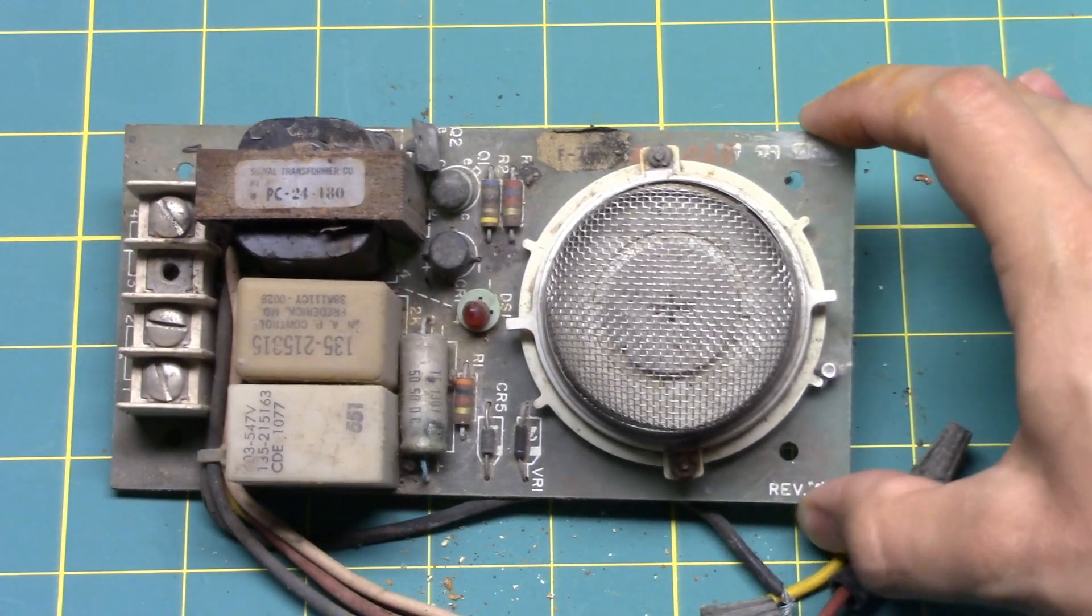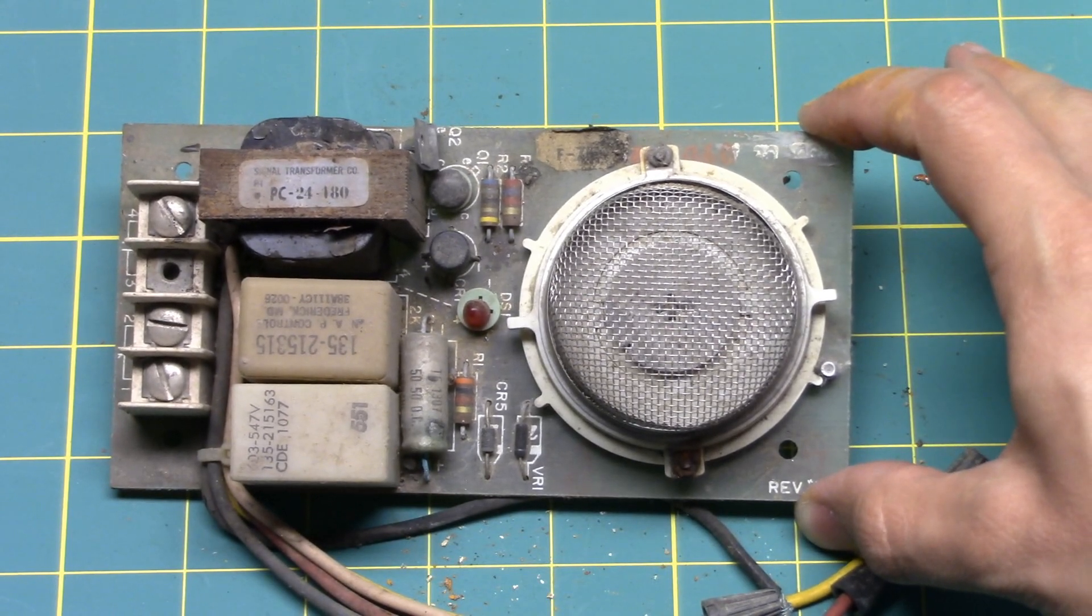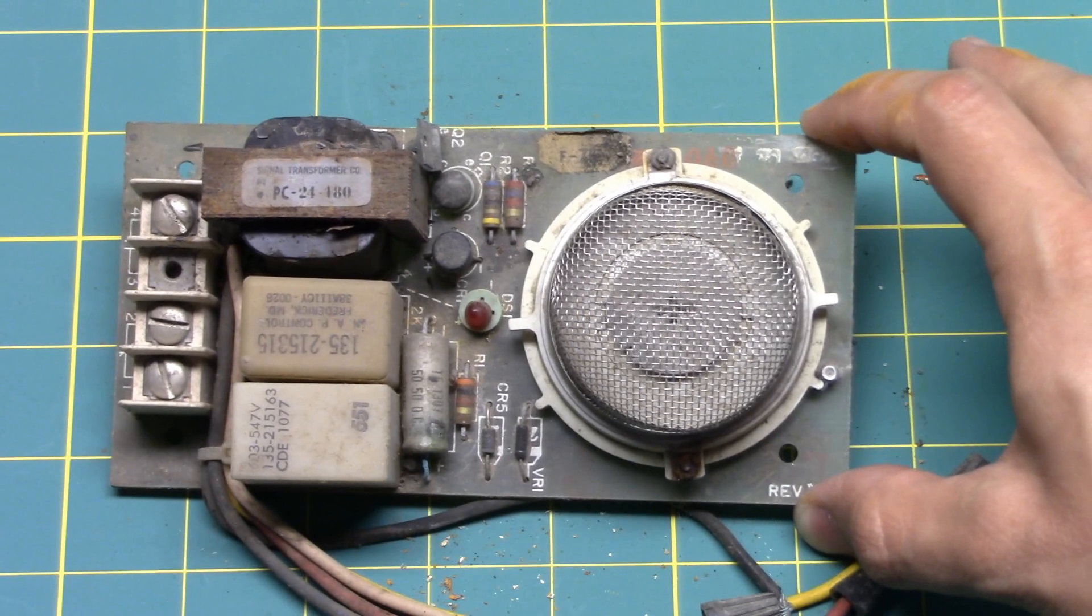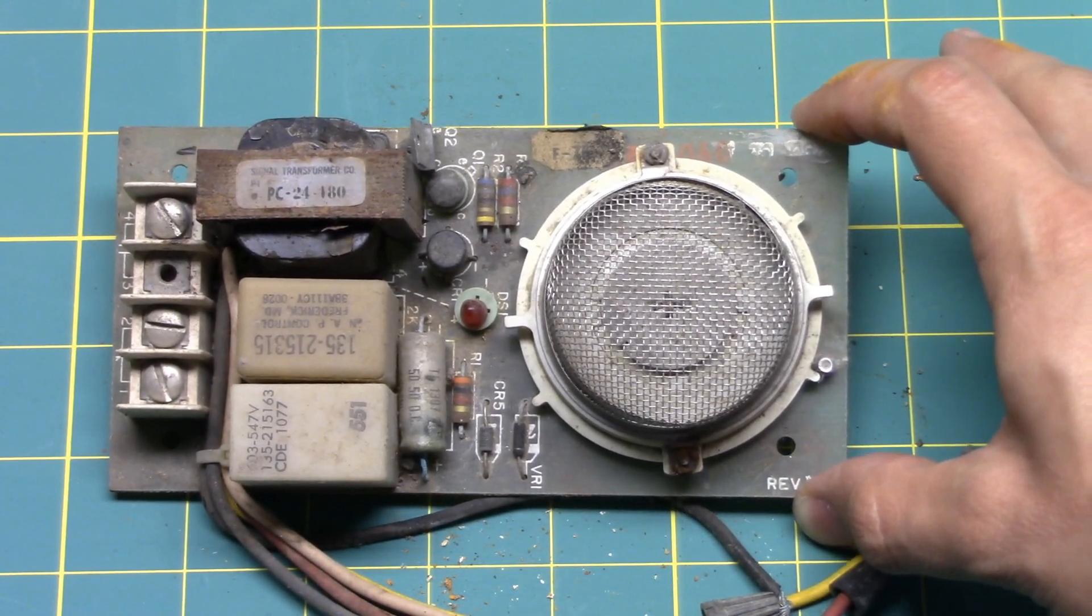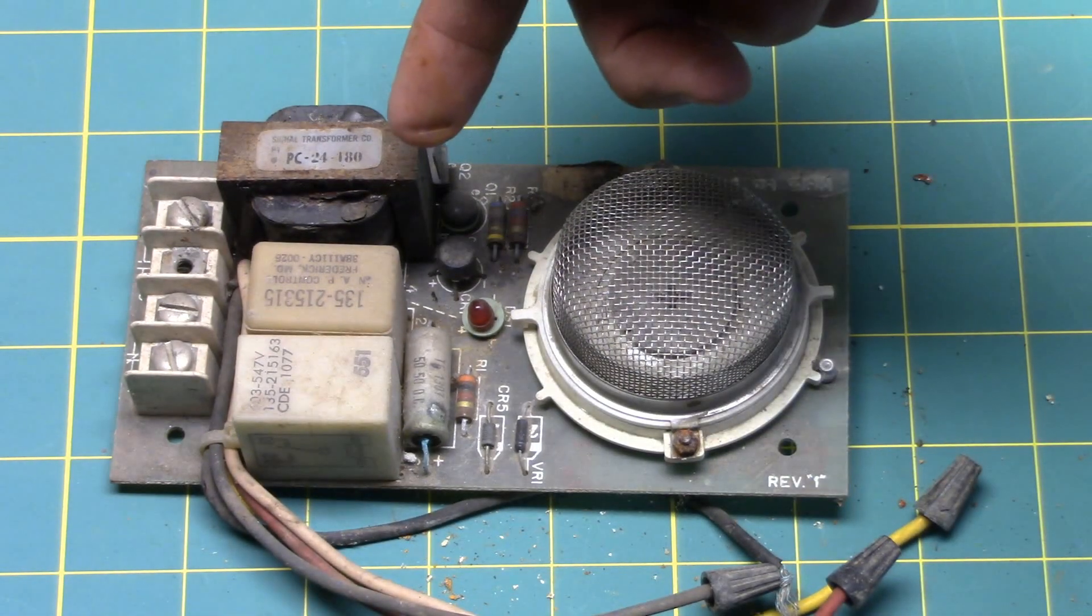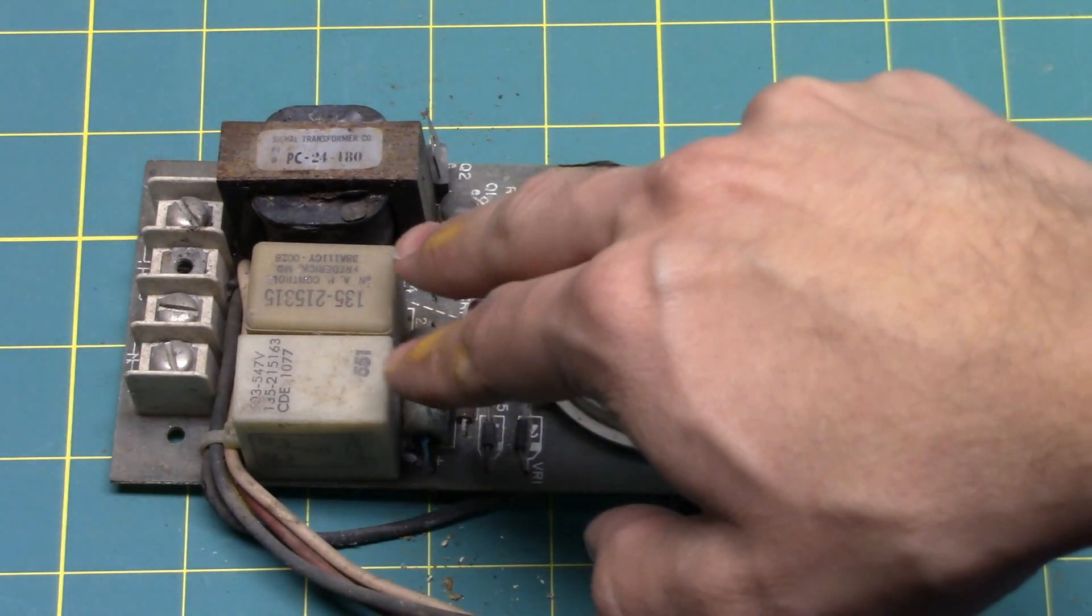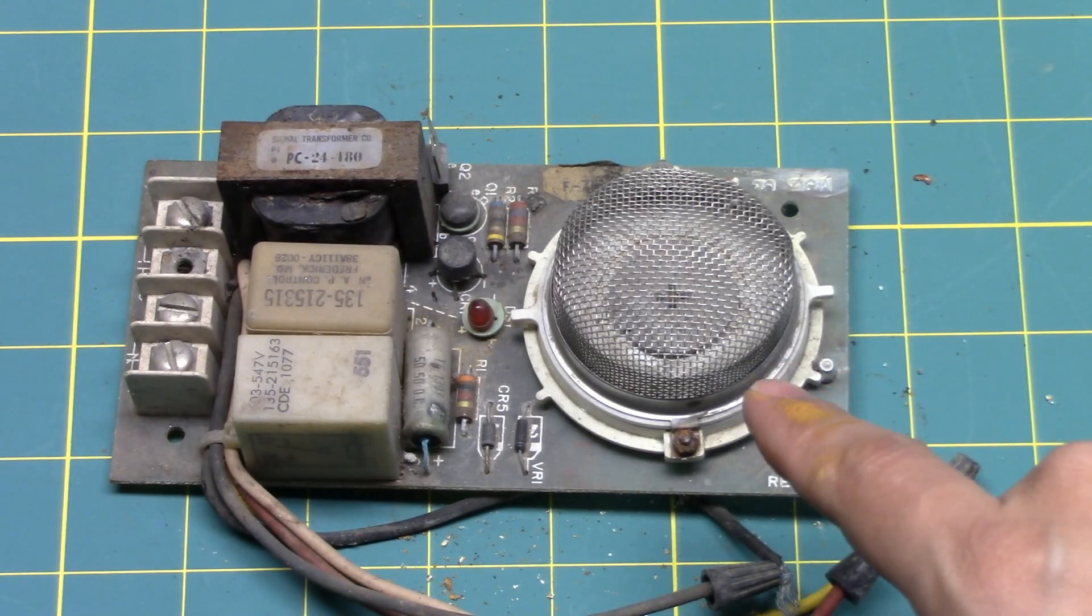Let's take a look at one in better condition. So here is a vintage Pyrotronics smoke detector circuit board or smoke detector module. Now this was part of a commercial building's fire alarm system. So you'll notice this detector does not contain an alarm horn. You notice it contains a power supply transformer, indicating LED, a couple of relays, and the ionization chamber.